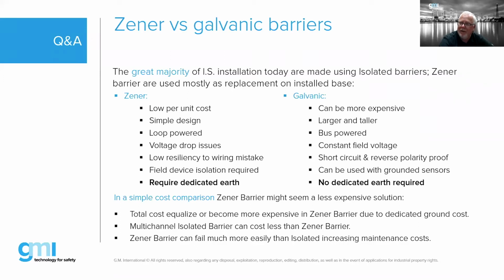We also did in the past that Zener barrier, and we had the same solution. What happens is you put a second fuse with a lesser value on the outside of the Zener barrier, or on a non-potted area, so you can remove it. But still, you have one inside that cannot be replaced. So you have a 50 milliamp inside, you put a 48 milliamp outside. So if you're lucky, you blow the one outside first.